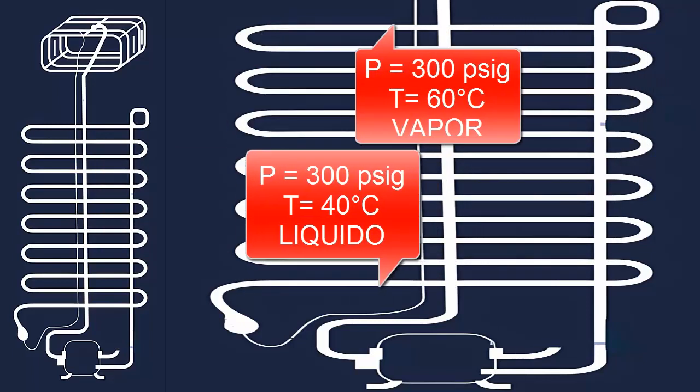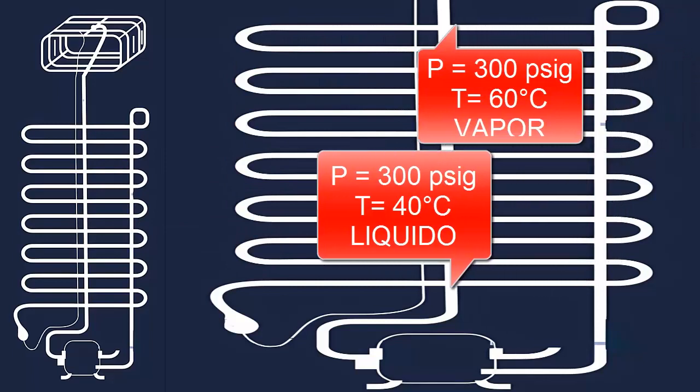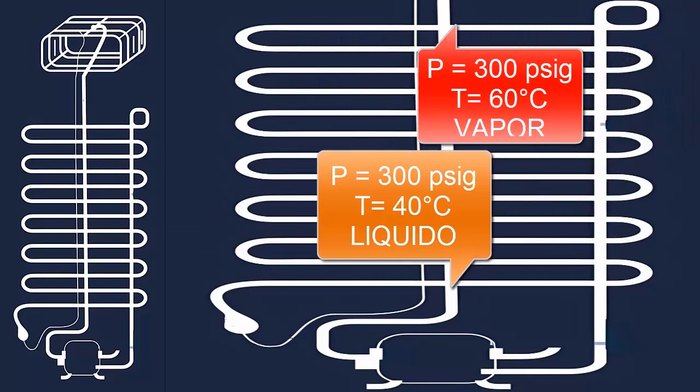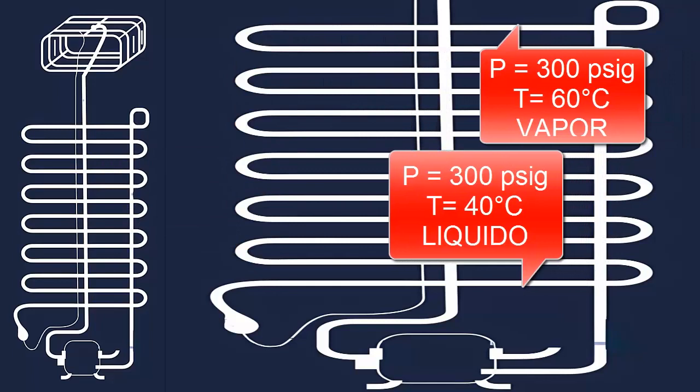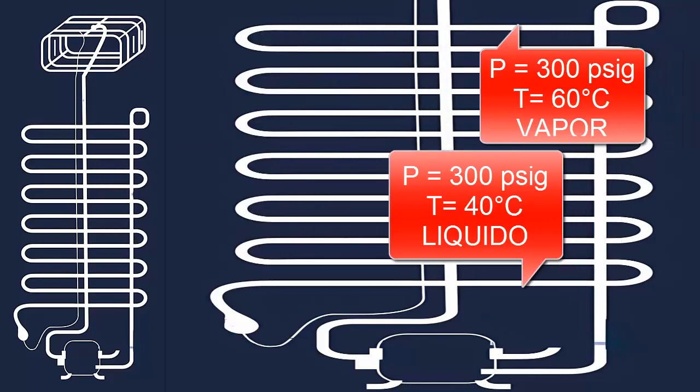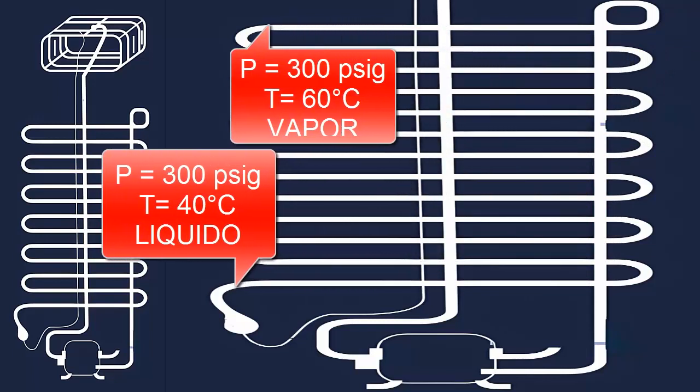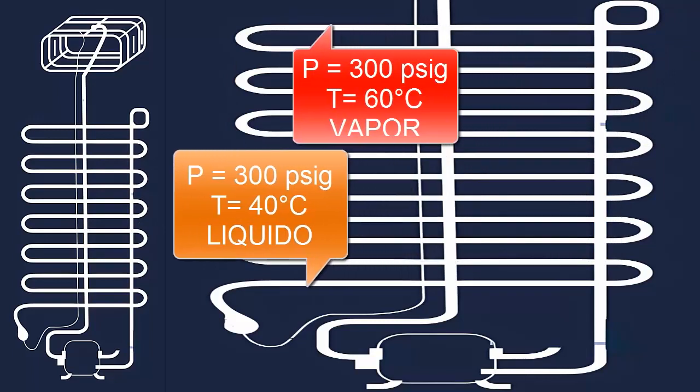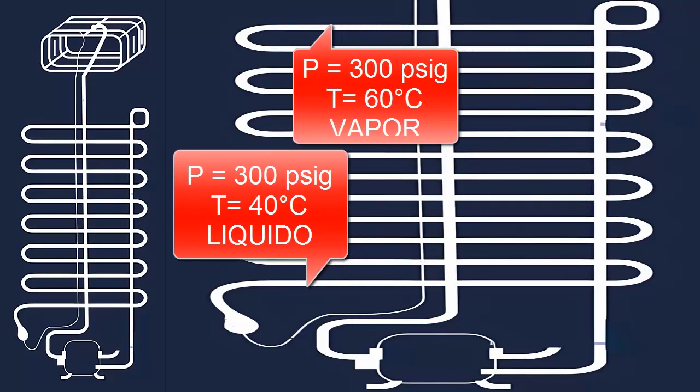As the R404A refrigerant loses heat in the condenser, it changes from a gaseous state to a liquid state. The pressure of the R404A refrigerant in the condenser remains at 300 pounds per square inch, but the R404A decreases its temperature considerably. This decrease in temperature of the R404A in the condenser allows the refrigerant to transition from a vapor state to a liquid state.